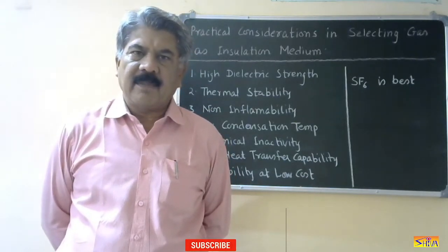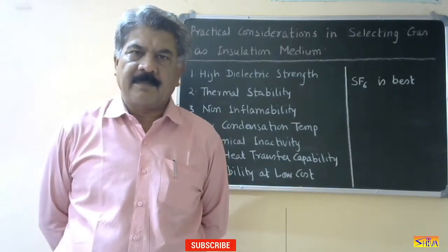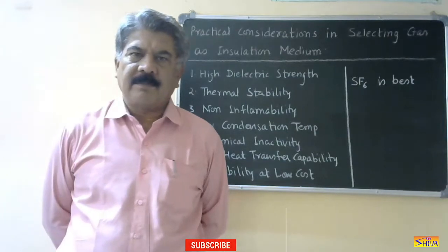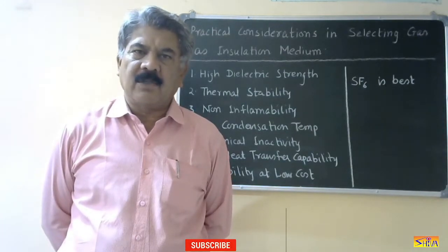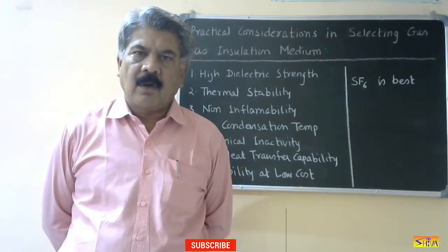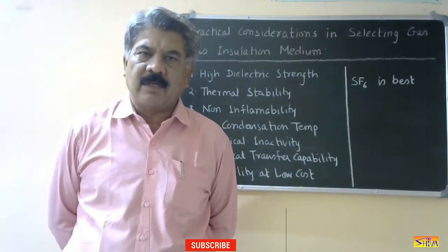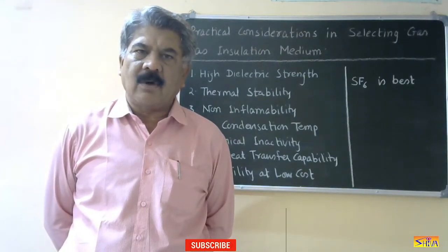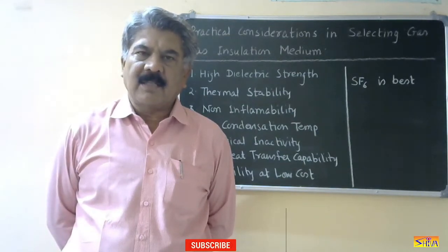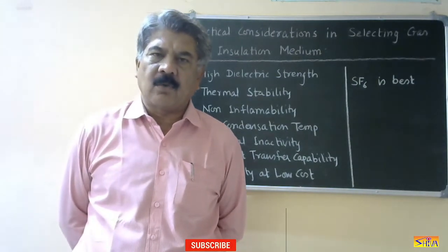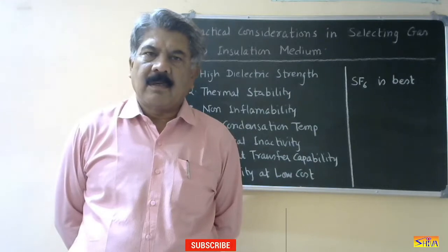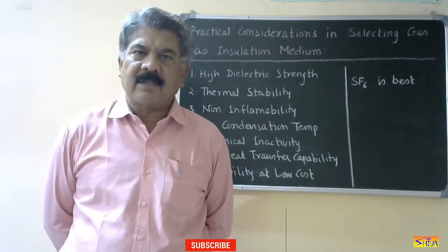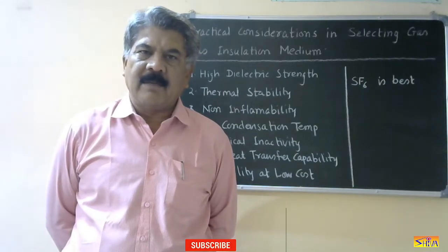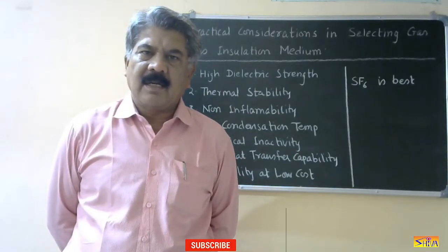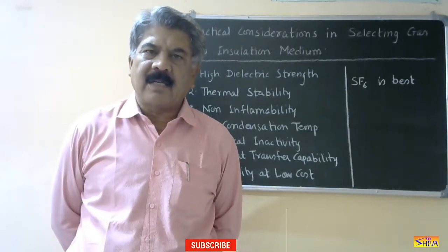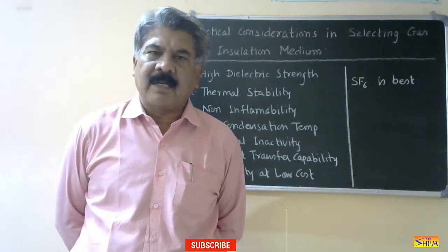I will take the example of transformer and circuit breaker. In air-cooled transformers, the air is used as insulating medium as well as cooling medium. On one side, it is in contact with the insulation of the winding, and on the other side, it is in contact with the body of the transformer. In case of circuit breaker, when circuit breaker contacts are closed, it is acting as cooling medium, and when circuit breaker contacts open, it acts as insulating medium between the electrodes as well as it acts as arc quenching medium because arc is generated between the contacts when circuit breaker opens.